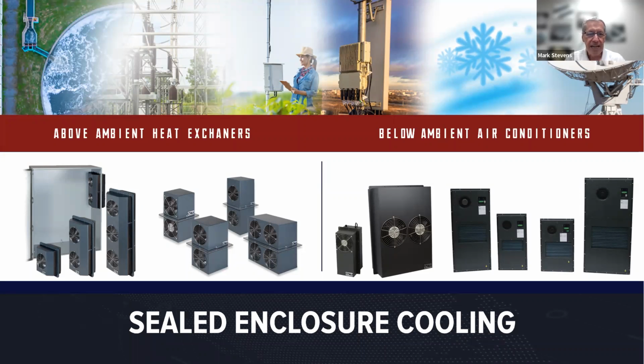cooling. But that again means that the outside of the cabinet has to be colder than the inside of the cabinet. If you have the reverse, where the outside of the cabinet is hotter than the inside of the cabinet, we go with our below ambient coolers, which Devin is going to speak about at the end of the presentation, and that's our air conditioning line.